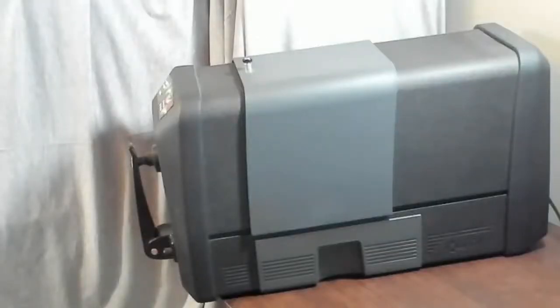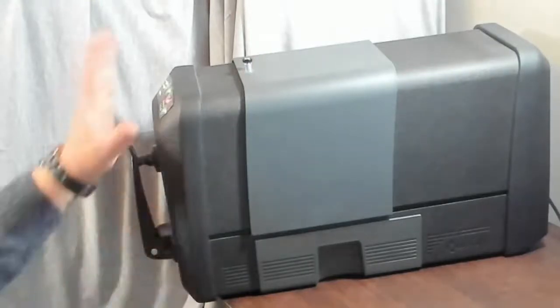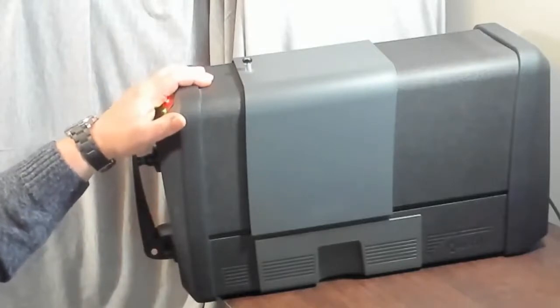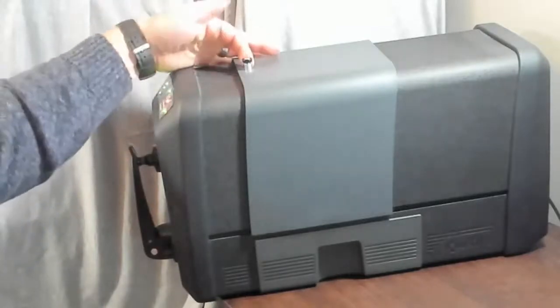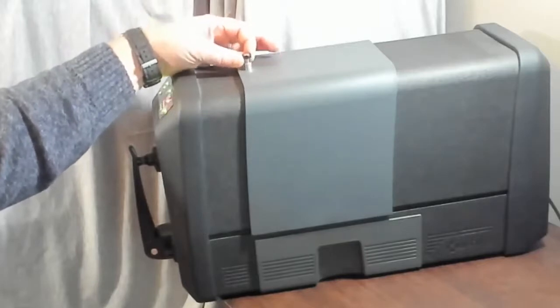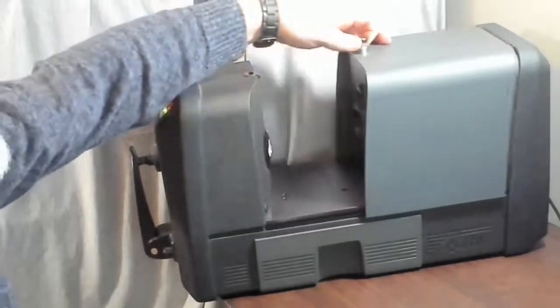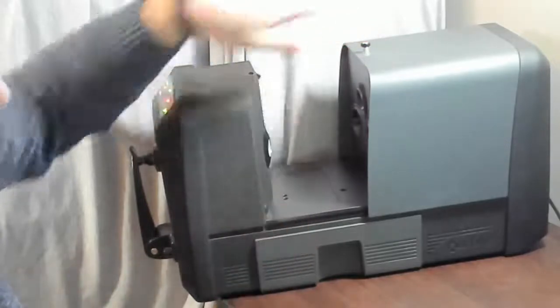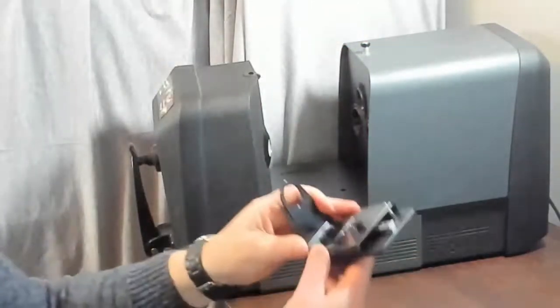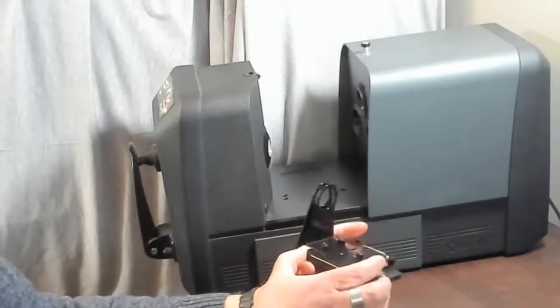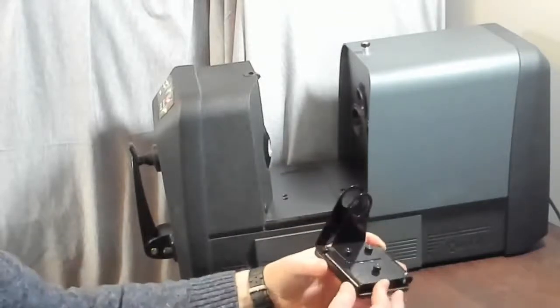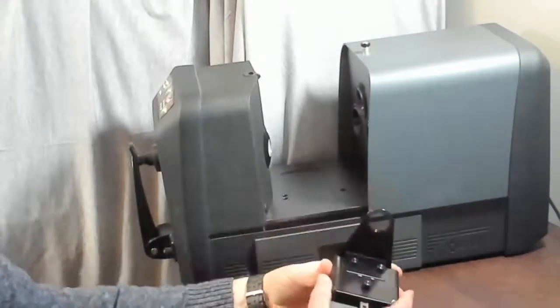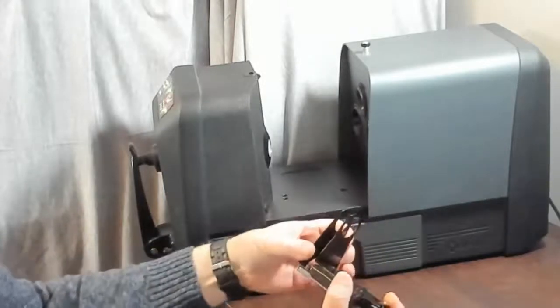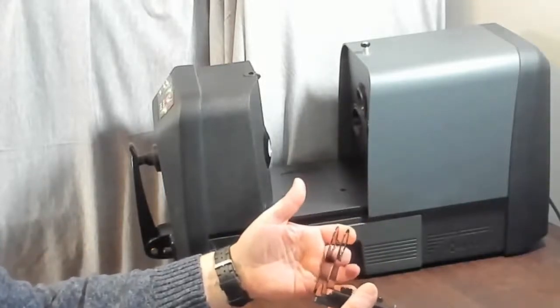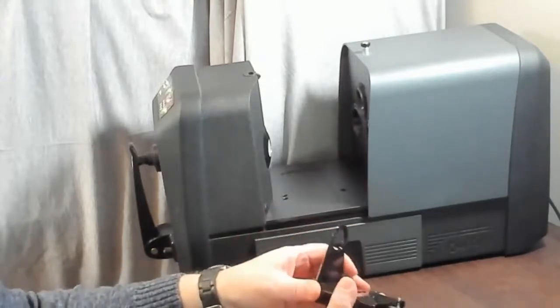So now that we've reviewed the various pieces inside the transmission kit, let's put them to use. So here is my Ci7800 instrument. To start, I'm going to open up the transmission compartment. To do that, I simply pull up on the spring-loaded latch, and I can slide the door back. That gets me access to the compartment. So the first piece I'm going to need is this film holder, which I've assembled from the kit. I've got the 25 millimeter aperture pieces in place. You'll see that there are 2 of them, and it essentially works like a clamp, a spring-loaded clamp to hold the sample in place.